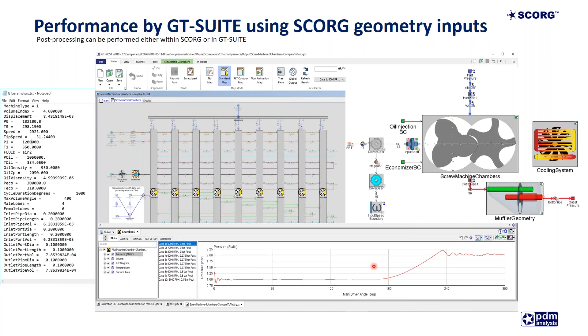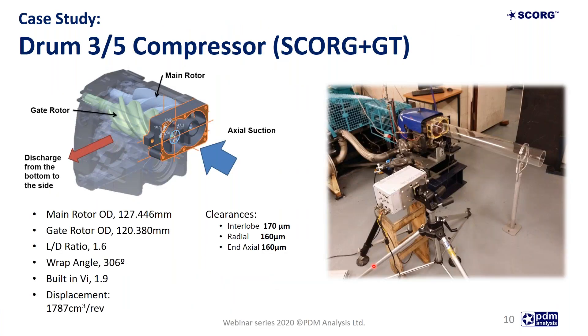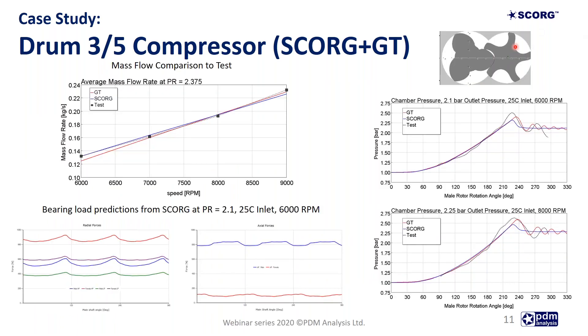I will hand it now to Alex to talk about examples of calculation of these machines using SCORG and GT Suite. The first case study was performed on an oil-free screw compressor with a 3+5 configuration of rotor lobes and N rotor profile, using both SCORG thermodynamics and GT Suite. The compressor was measured in the laboratory of City University of London.